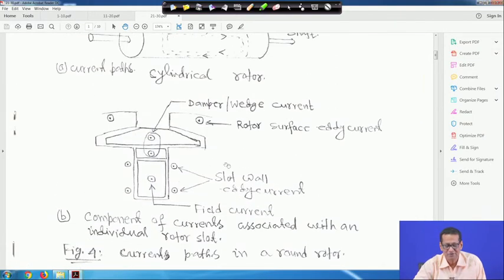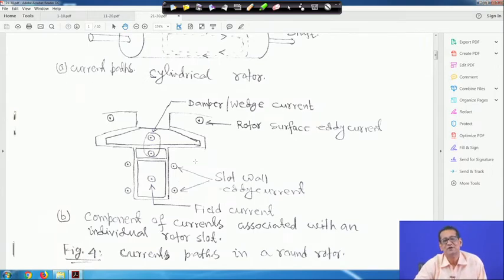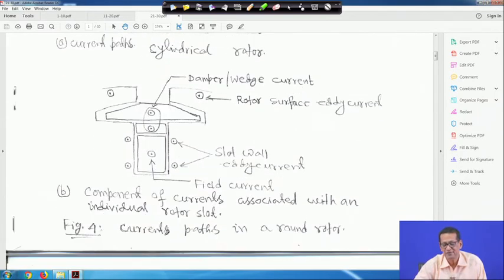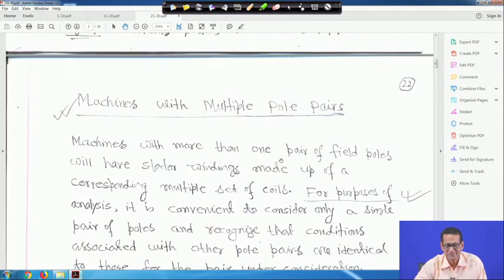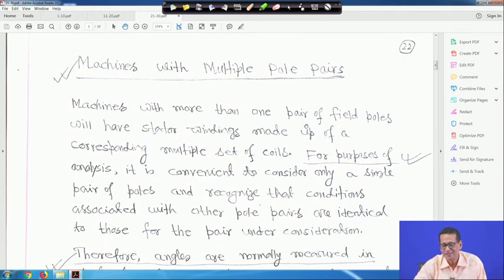Salient pole machines are generally used for hydro generators, while cylindrical rotor machines are used for thermal power plants — steam turbines or gas turbines. For machines with more than one pair of field poles, the stator winding is made up of a corresponding multiple set of coils. For analysis, it is convenient to consider only a single pair of poles, recognizing that conditions for other pole pairs are identical. Therefore, in this course, only the two-pole machine (one pole pair) will be considered.